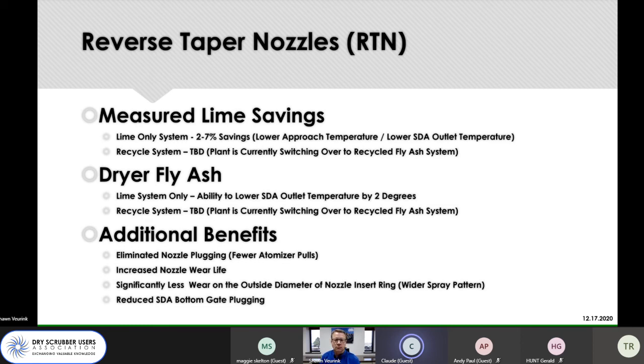Coming off the nozzle on the original style, there's a pretty large flat area on the nozzle outlet, whereas the ring has a circumference on it. That flat spot on the nozzle would cause an upset flow condition around the ring, creating pretty dramatic wear patterns on our ring.